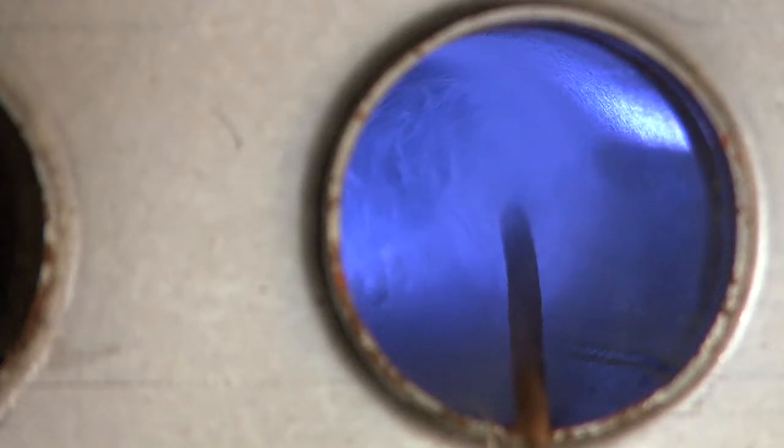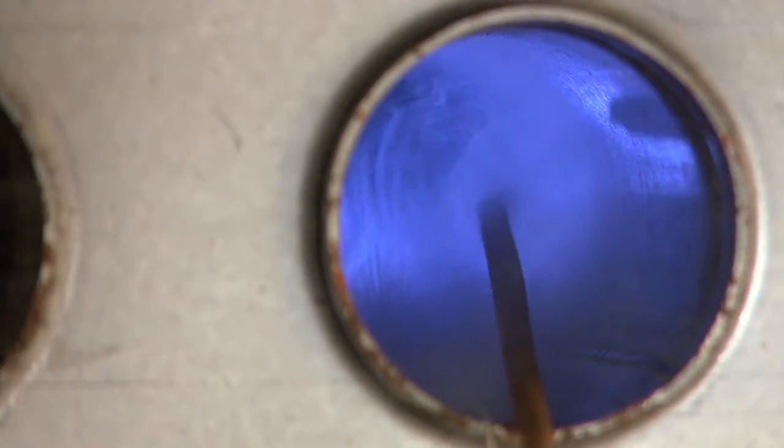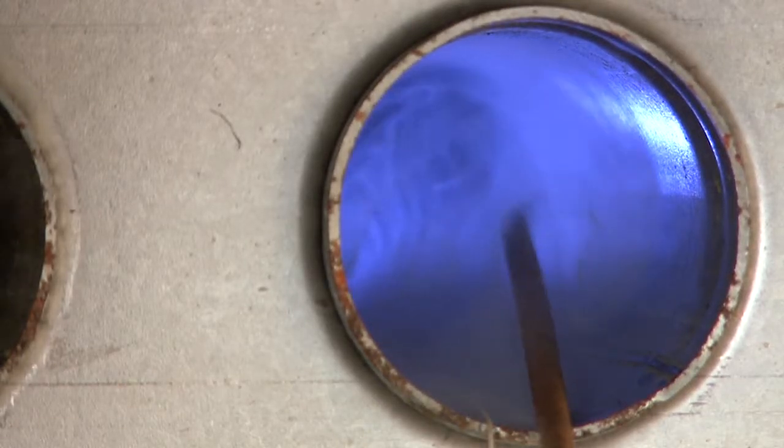But I let the smoke linger up in there for quite a while. I don't know, 30 seconds, maybe a minute, and just let that smoke build up in there. And then as long as you don't see any smoke movement, go ahead and move on to the next cell.